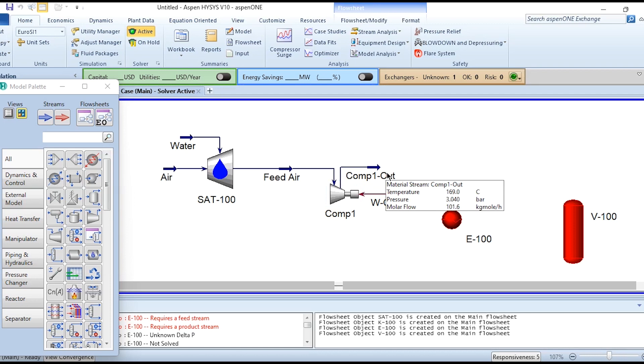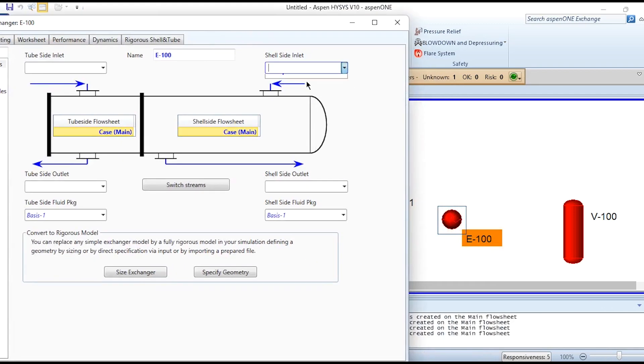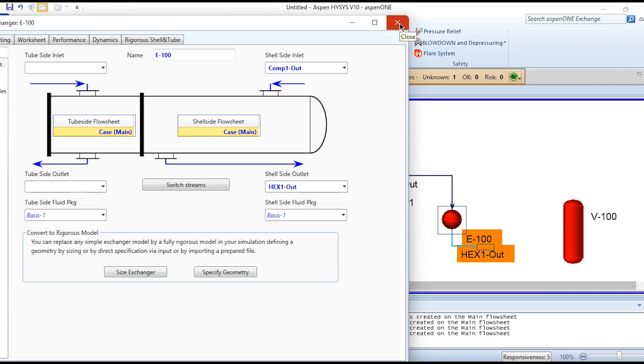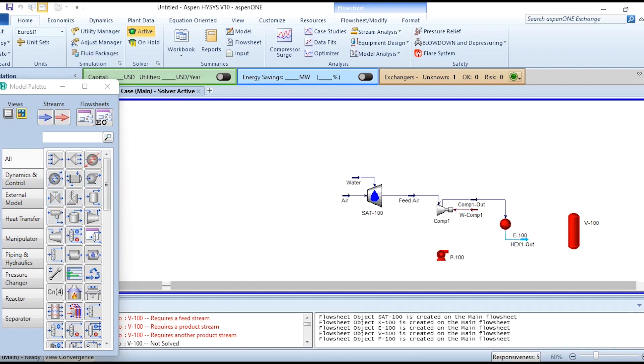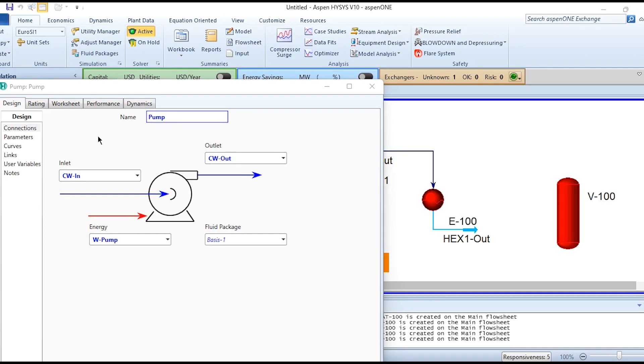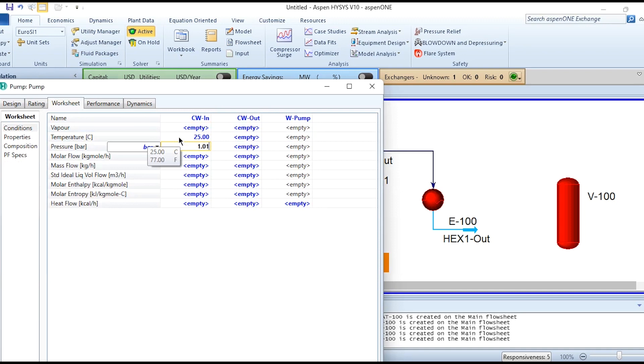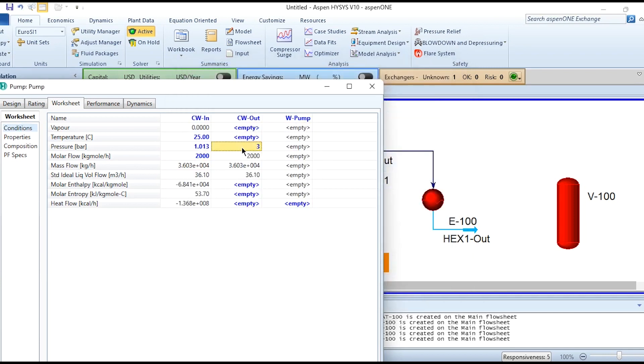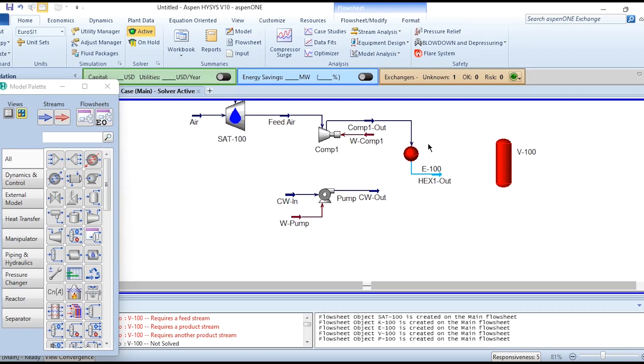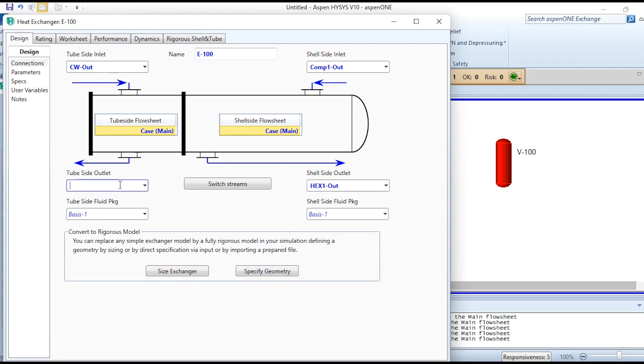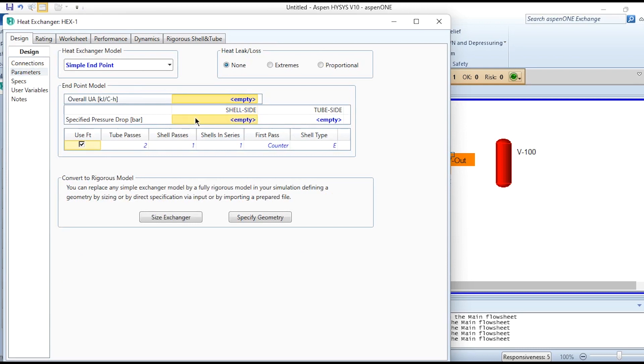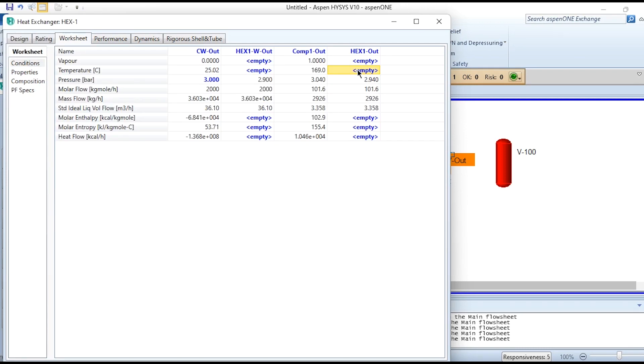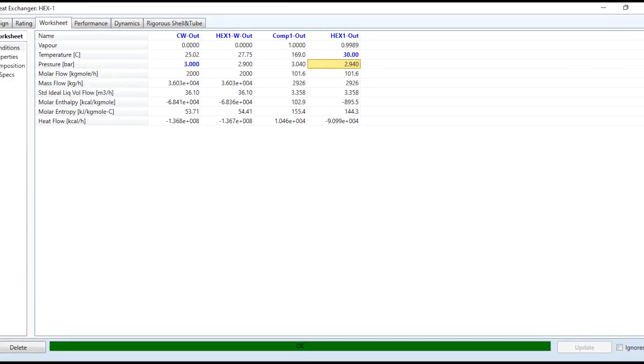The outlet air from compressor one goes to heat exchanger one, with Comp1-Out on the shell side and HEX1-Out as its outlet. For the cooling water side, we select a pump and connect: cooling water in, cooling water out, and work required for the pump. Cooling water is specified at 25°C, 1.01325 bar, 2000 kg-mol/hr, composition water = 1, and pump pressure ratio of 3. The cooling water outlet is connected to the tube side of HEX1, labeled HEX1W-Out. Pressure drop is 0.1 bar on both shell and tube sides, outlet air temperature is 30°C, and the heat exchanger converges successfully.